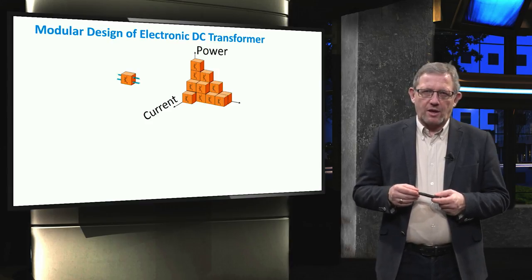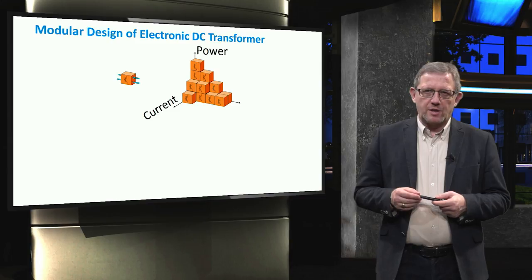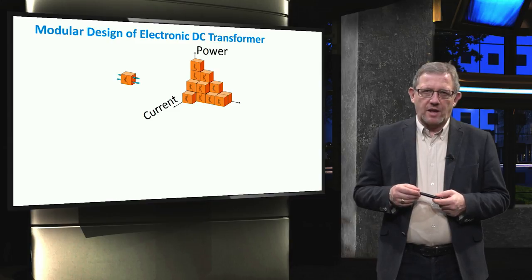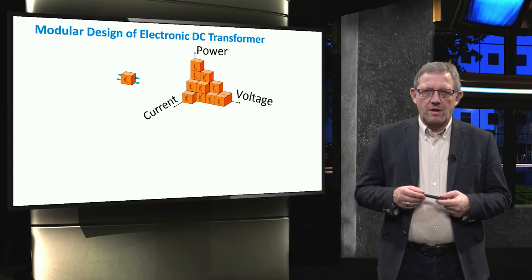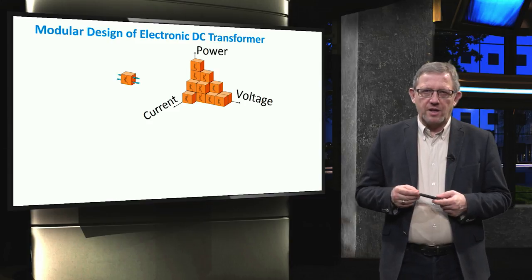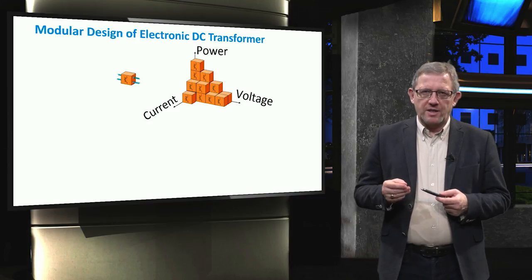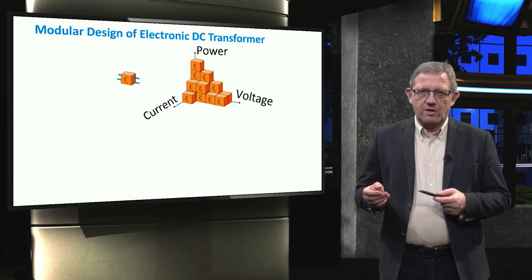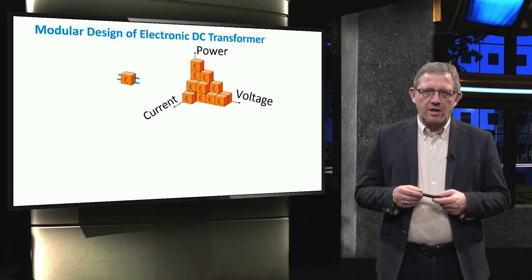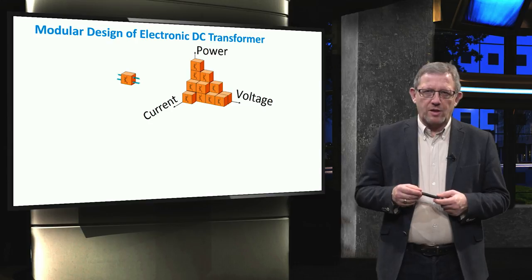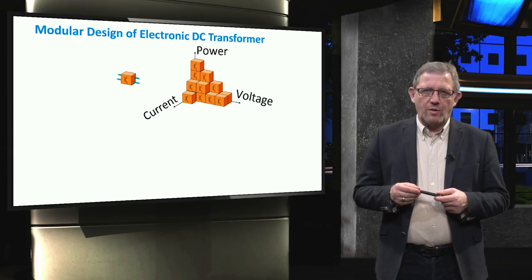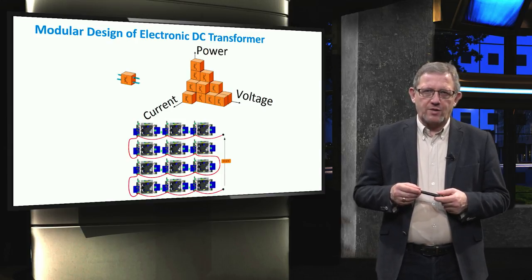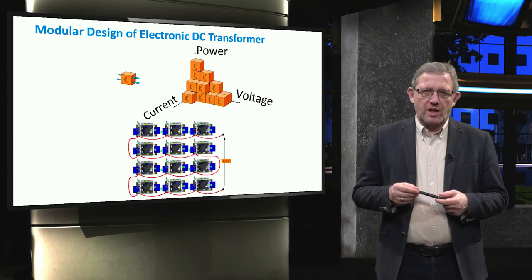If the modules are connected in parallel, then it is possible to increase the current capacity. If the modules are connected in series, then the overall voltage rating will be increased. Using parallel and series connections, it is possible to build up high power electronic transformers in a modular way, where an example of 16 modules in series to reach 10 kV is shown.